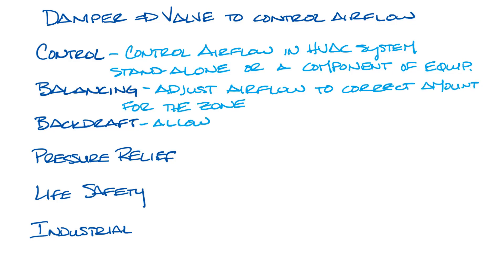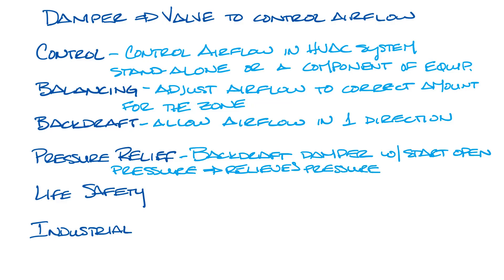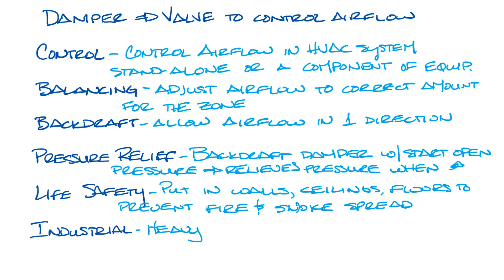Backdraft dampers allow airflow in only one direction to prevent backdraft. Pressure relief dampers are backdraft dampers that have a set-open pressure so that if the pressure exceeds that predetermined point, the damper will open and allow the pressure to be relieved. Life safety dampers are put in openings in walls, ceilings, and floors to prevent the spread of smoke and fire. Industrial dampers are heavy-duty dampers used in severe conditions, such as applications like tunnels and blast situations.